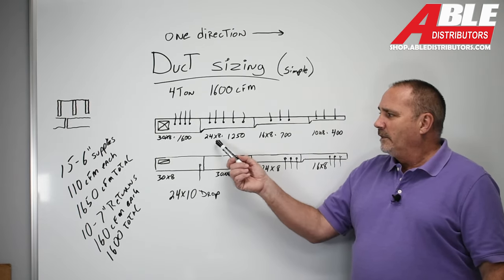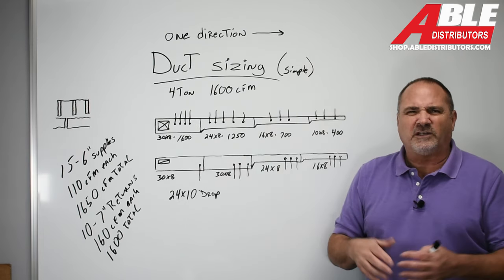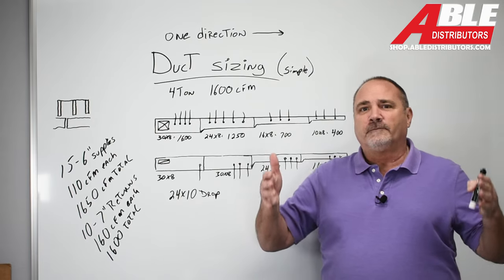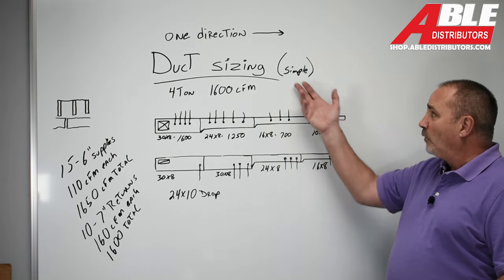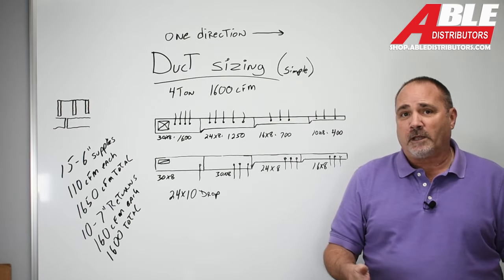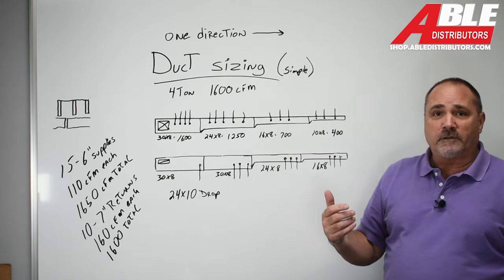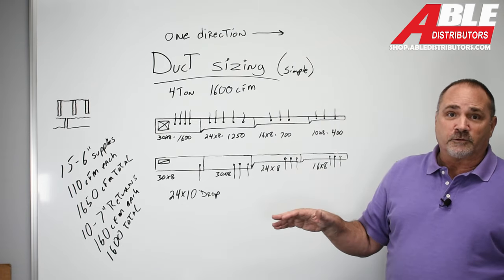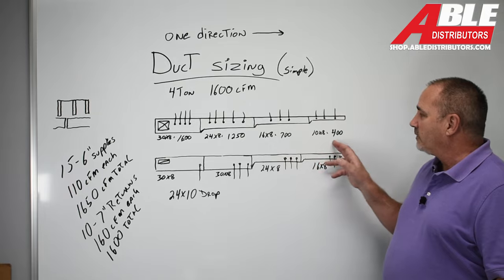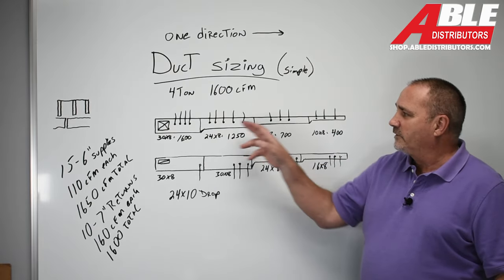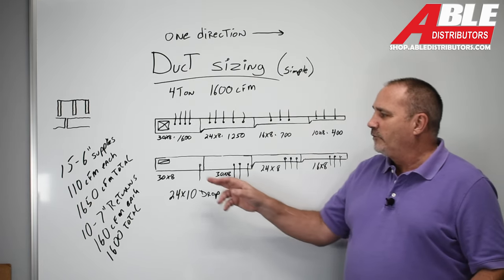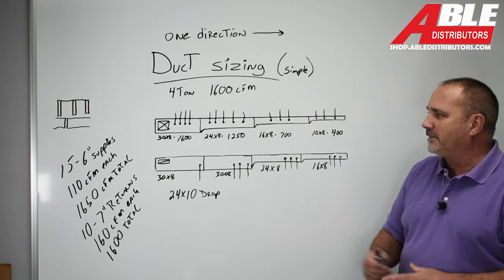So if you can see, when I reduced, this actually came up to be 22 by 8. Honestly, most supply houses stock standard sizes. And this simple routine is you're not making anything weird. You can just run to any supply house, buy all the ductwork, buy all the transitions, and make it super simple. And you don't have to have a shop at all. So that's how I did the supply, figuring 15 six-inch supplies, all with top takeoffs, all pretty simple.